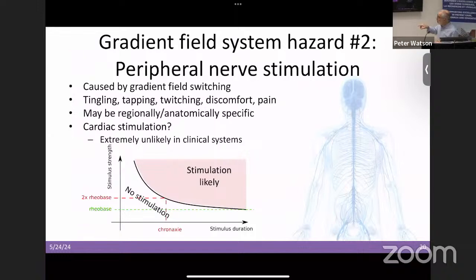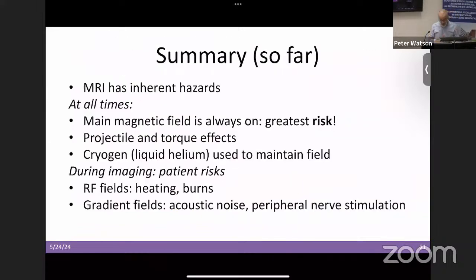So if you see the plot here, what you have is stimulus strength on the y-axis and stimulus duration on the x-axis. And there's this region of operation that remained white, where we have the no stimulation words come up. Whereas if we can keep in these regions of operation, we are extremely unlikely to produce nervous stimulation. So far, I've talked about MRI and its inherent hazards, some of which are on at all times, and some of which are on only during imaging and mostly concern the patient.